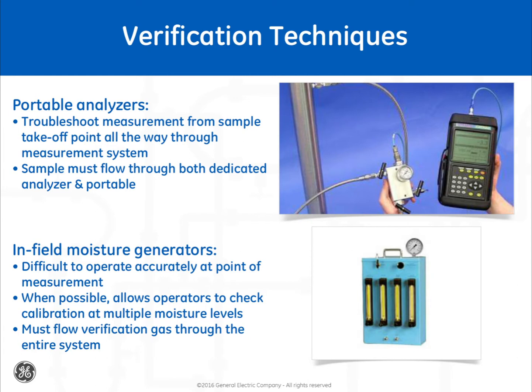Two common methods employed for verifying the performance of a dedicated moisture analyzer are portable moisture analyzers and in-field moisture generators. A portable moisture analyzer is a powerful tool to verify the performance of a dedicated analyzer. Since it can have an integral sample system, one can use a portable analyzer to troubleshoot the moisture measurement system, starting from the outlet of the sample system all the way back to the sample takeoff probe, until the root cause of the discrepancy can be found, or until this method verifies the measurement of the dedicated analyzer.